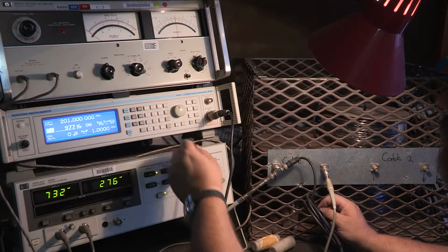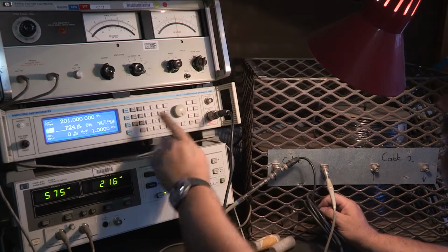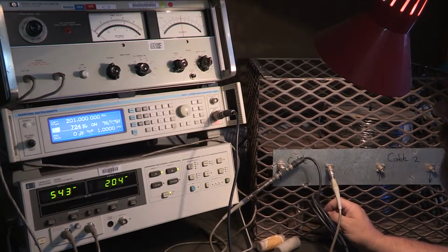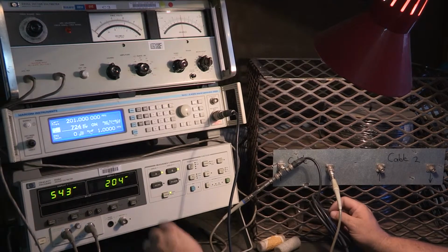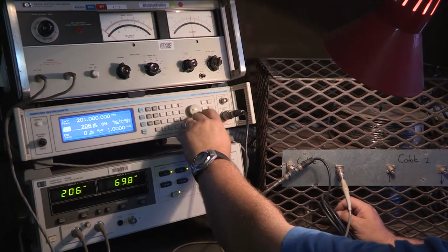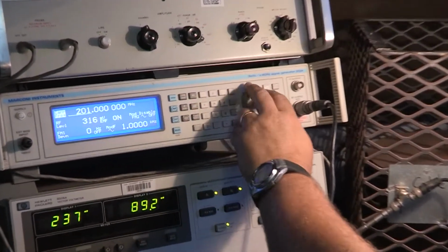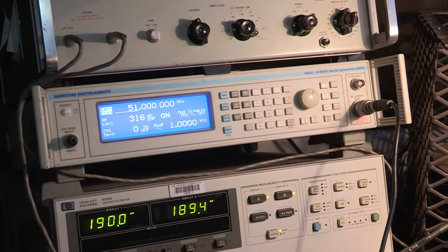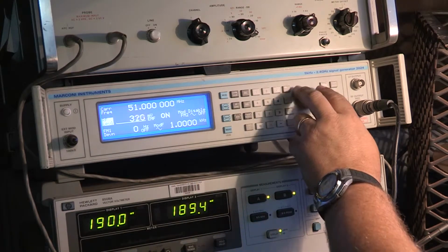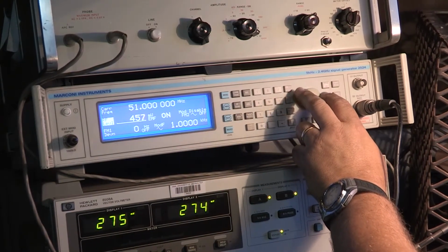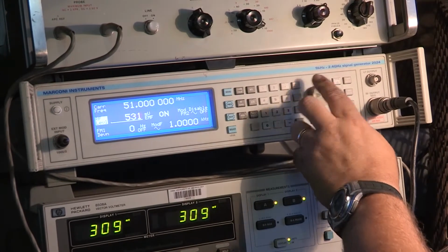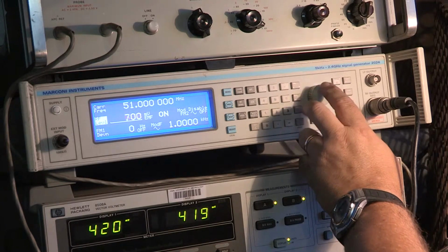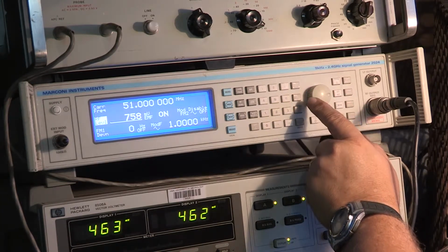Once we have that, we can choose all kinds of frequencies, and we need to adjust channel A every time so that the readings can be done accurately. So, starting at 50 megahertz carrier, 50 megahertz is around about here. Then with the RF level, we make sure we get a starting point. It can be anything. It doesn't need to be 730 for your first reading, but since we have already started and we've got something useful there, let's choose that one.